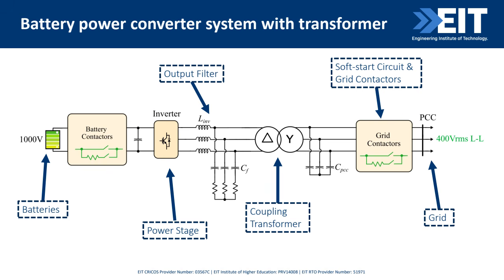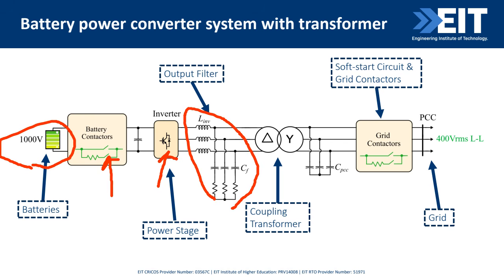Now let's look at a simple, conventional way of connecting a battery system to the grid. In this configuration, I have the battery rated at 1000 volts and a two-level inverter. I would need some contactors and pre-chargers on the battery side, and at the output of the inverter we normally have LC filters or an L filter, and so on. In this case, the power converter uses a transformer for connecting to the grid. That gives an overview of a simple power converter for connecting the battery to the power system.